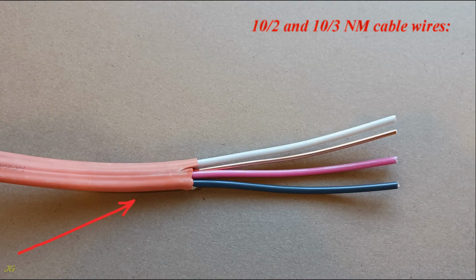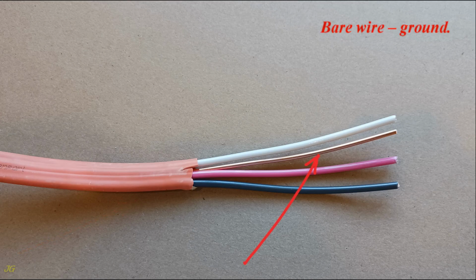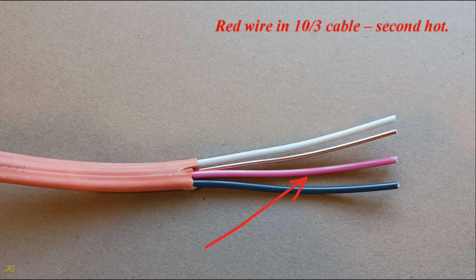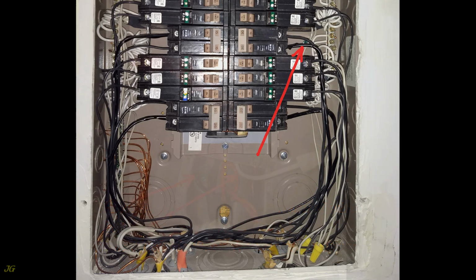10-2 and 10-3 NM cable wires. Bare wire, ground. White wire, neutral. Black wire, hot. Red wire in 10-3 cable, second hot. When using 10-2 cable, the neutral wire is used as the hot wire and must therefore be marked as a hot wire with black electrical tape or other appropriate means.